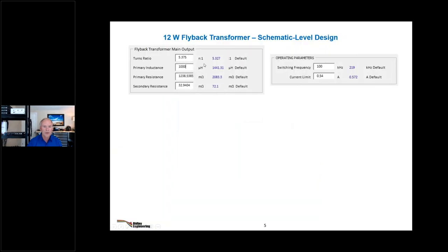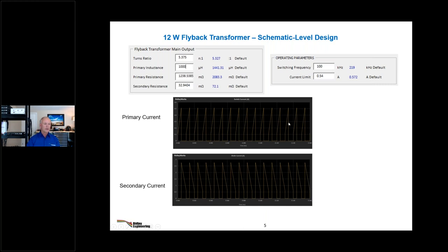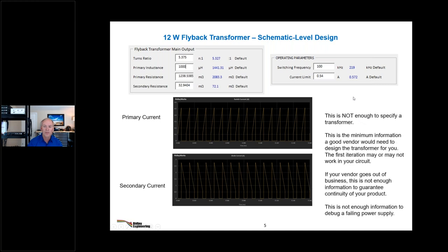You can give these parameters, the switching frequency, the current limit, and the waveforms, to a manufacturer at this point, and a good qualified manufacturer will be able to build you a transformer from this. However, this is not a specification for a transformer, it's the minimum information a good vendor would need to design the transformer for you. But it's not enough information to recreate that transformer if something goes wrong, if your vendor goes out of business. Hopefully they don't, but you have to worry about those things these days, about continuity of your product. So having this data about your transformer is not enough to guarantee that.